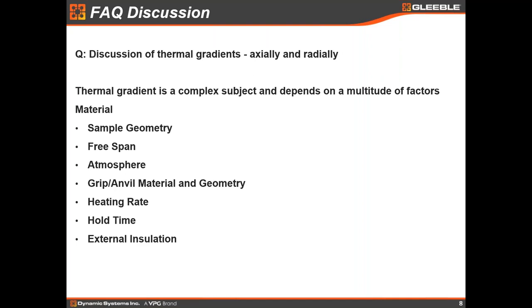There are a lot of factors that go into controlling the thermal gradient in a Gleeble sample. The first is sample geometry — is it a compression or tension sample? Six millimeter, ten millimeter, plane strain? All those will affect the thermal gradient. The material will affect the thermal gradient because it affects both the electrical and thermal resistivity, which have big components in the thermal gradient. The free span that you use, the atmosphere — vacuum, inert gas, or air — will have a big role as well. Obviously, the grips and anvil material, the heating rate, and any external insulation on the sample also matter.